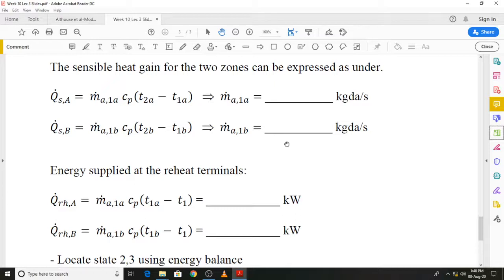And the equation, because it's sensible heating, is the same: the energy transfer rate is equal to the mass flow rate times the specific heat times the temperature difference. And remember, the air after the cooling coil is at a temperature T1, or you can say T6 or T7, they are all the same, and that air is heated by the individual reheat terminals. So it will be heated to a temperature T1A for zone A, and to temperature T1B for zone B accordingly. So the reheat energy requirement for zone A is equal to the mass flow rate for zone A times the specific heat times T1A minus T1, and once you put in the numerical values you will get the desired energy transfer rate in kilowatts.